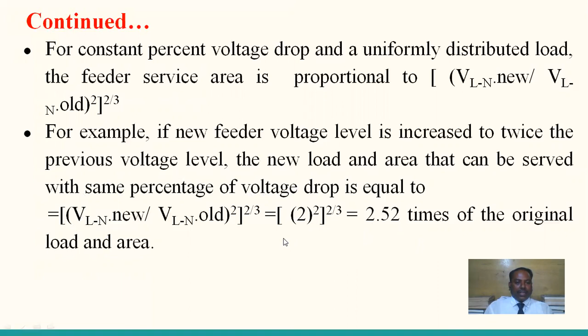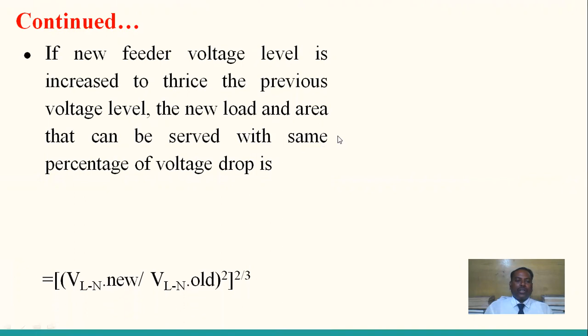As per the voltage square law, the feeder service area as well as load is 2.52 times the original if voltage is doubled, which covers 2.52 times the original load as well as the area. For example, if feeder voltage level is increased to thrice the previous voltage level, the new load and area that can be served with the same percentage voltage drop is 4.32 times the original load and area it covers. Yes.